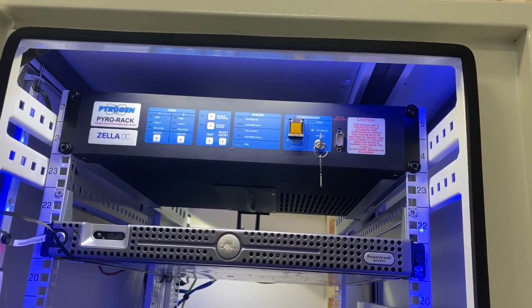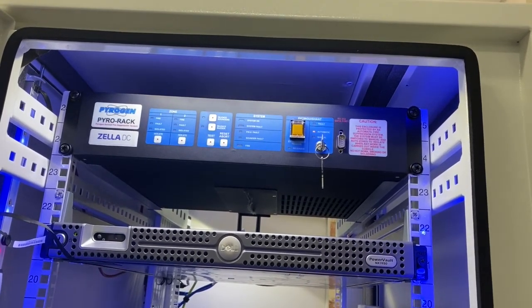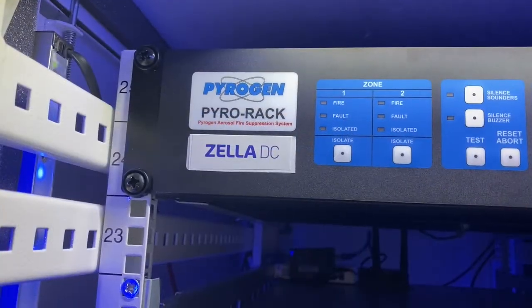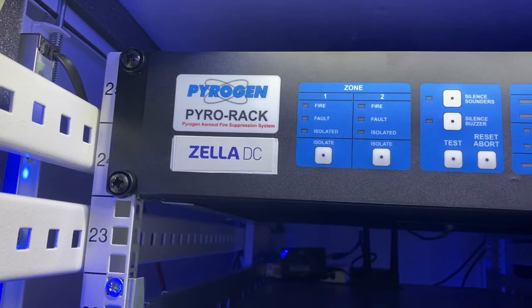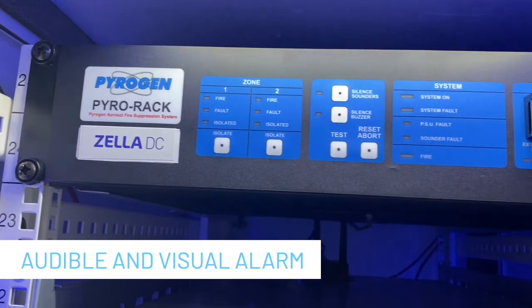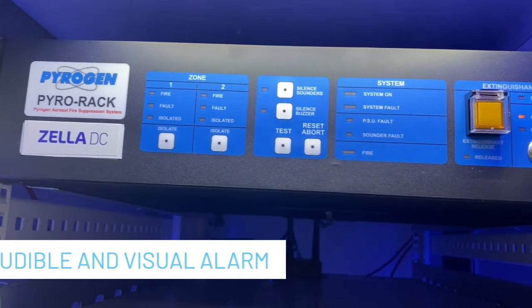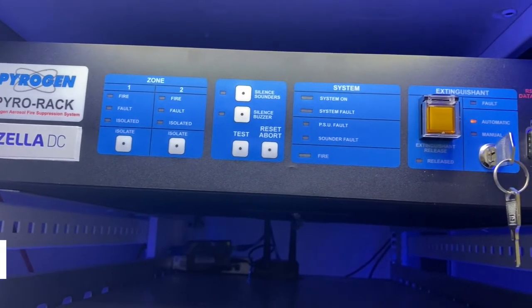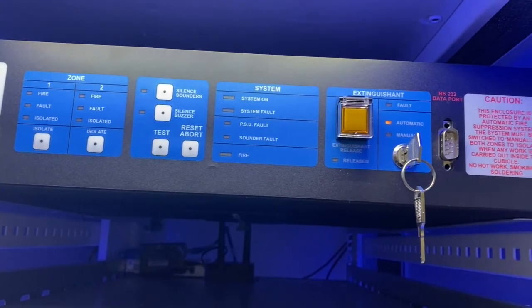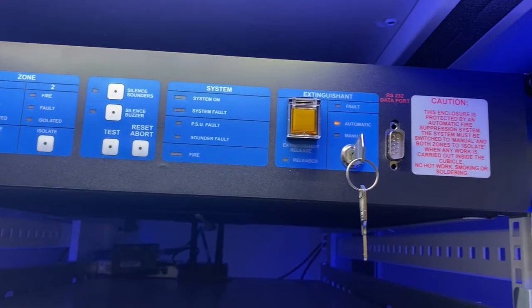Should a smoke detector sense smoke, it will cause the Pyro-Rack to go into a fire alarm mode, providing an audible and visual local alarm that also remote signals a monitoring system. As a standard feature, the Pyro-Rack can also operate a 24-volt driven fire alarm such as a sounder beacon.